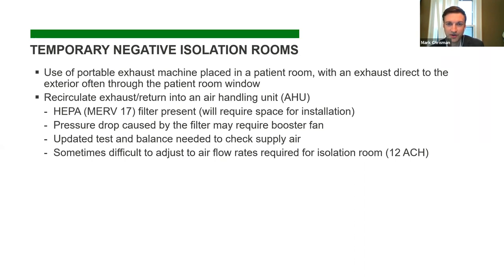Another option we looked at, but aren't highly in favor of, is just recirculating the exhaust or return air into an air handling unit. You can do that, but there are some challenges, one of which is you need to put a HEPA filter on that return duct in the room with a MERV 17 filter.